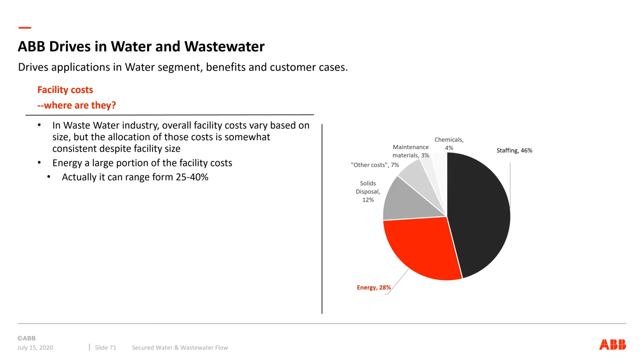Energy consumption: putting variable frequency drives on blowers or compressors in a wastewater plant, 50% or more of the energy is used just there. The next two biggest are pumping and aerobic digestion. Within those 3 sections, we've got 75% of the energy consumed in the plant, things we can put drives on, use controls, analytical equipment, and smart sensors for, controlling the entire plant off a set point based on actual flow and demand coming in, so we don't have to fine tune every operation separately. That makes us all much more efficient.